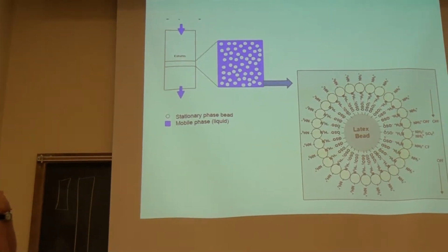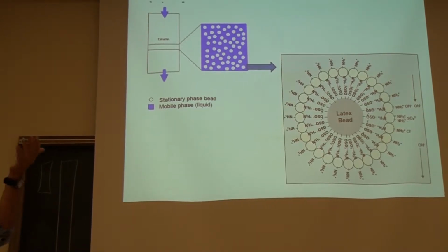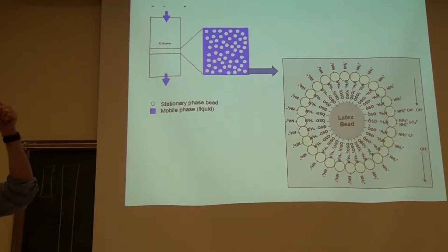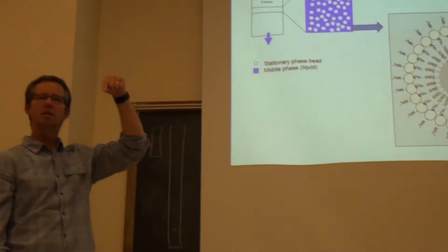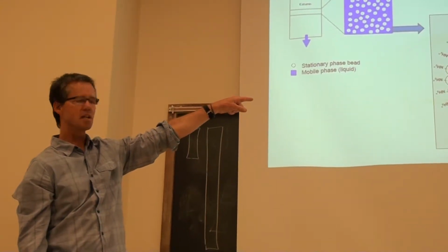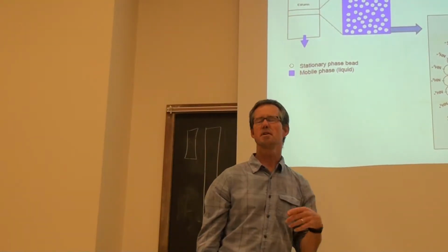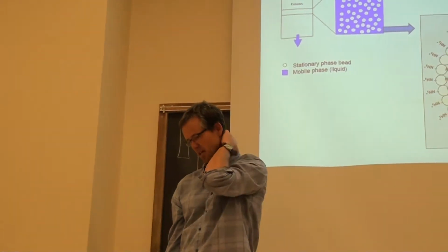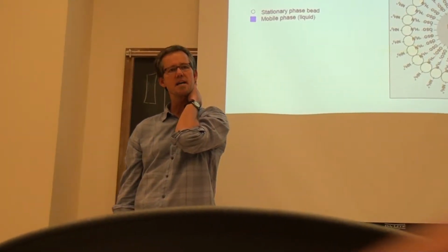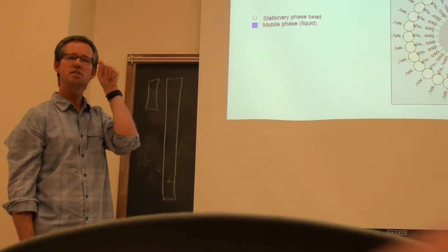And that's why most chromatographic systems, like the one you'll use, and like all high performance or high pressure, people use both terms, liquid chromatography, build up a lot of pressure in the fluid. It takes a lot of pressure to push the mobile phase through, because there's a lot of resistance because those beads are packed so tightly. And so the pressure in your system, I'm trying to remember what it is, it'll probably be about 1,200 psi.